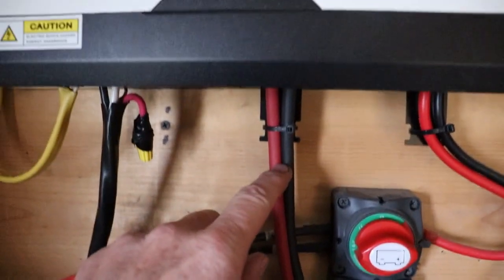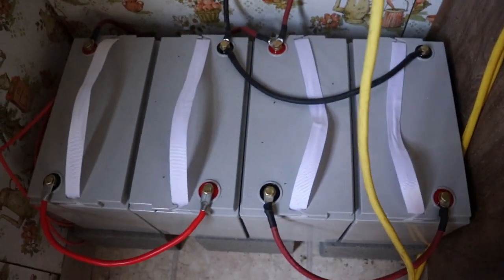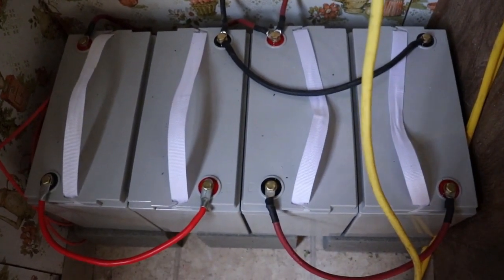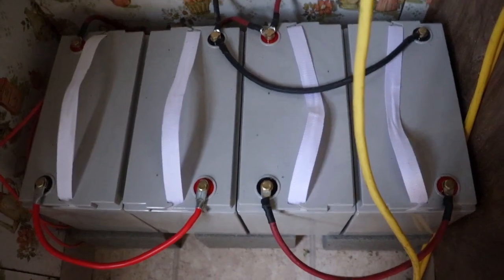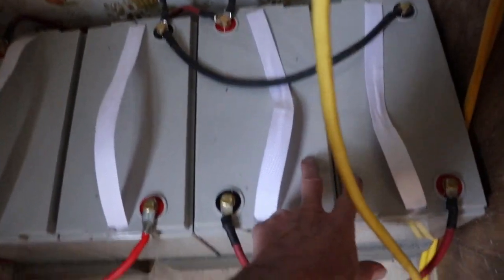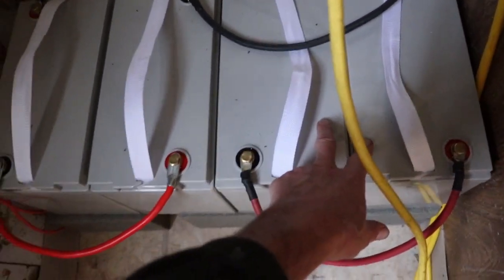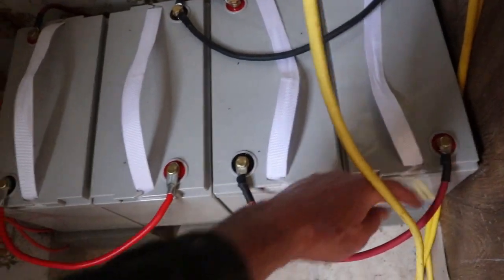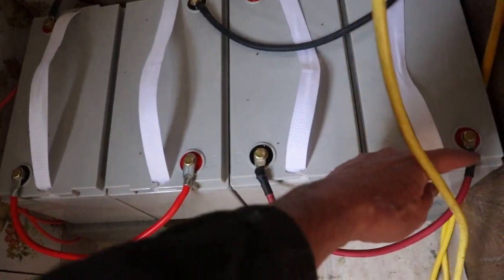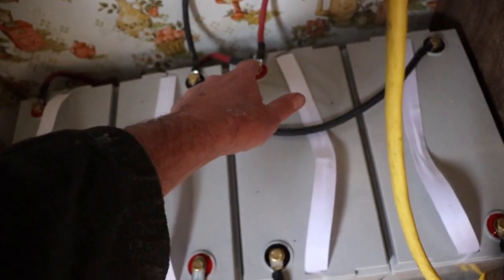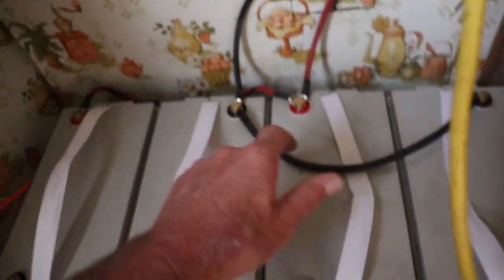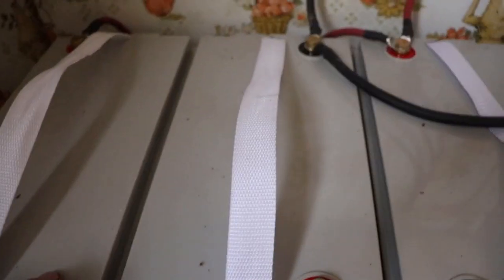This is the batteries, follow it down. I have 4, 100 amp hour lithium iron phosphate batteries, and there's 2 in series to make 24 volts, because it's a 24 volt unit. So you connect the positive to the negative, and then there's your ground, and there's your hot wire, your voltage DC plus positive. And I have the same thing over here.